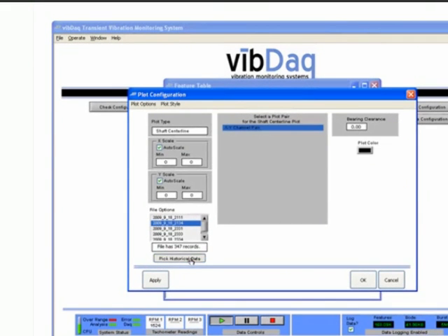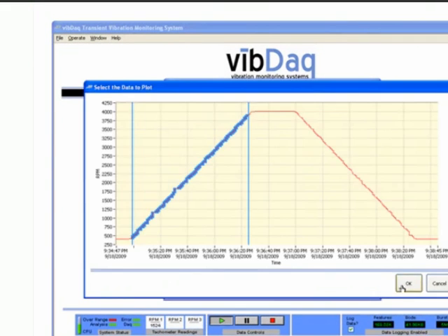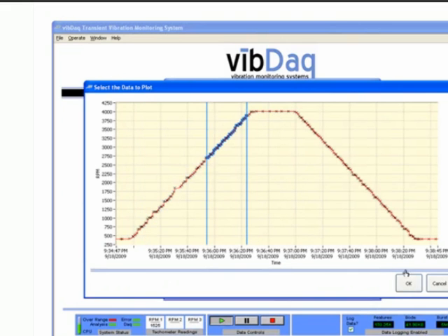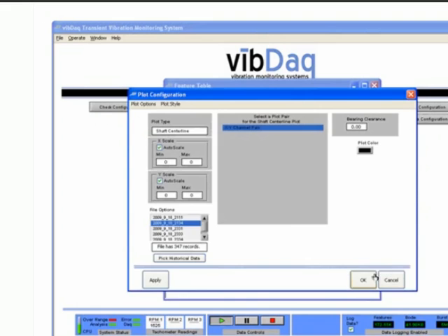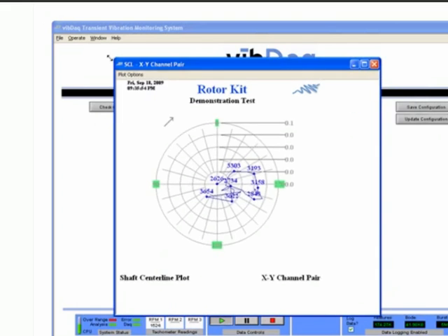Also using data from a channel pair, the shaft centerline plot shows the position of the shaft center at various speeds. The plot also shows a bearing clearance boundary. Knowing the path traveled by the shaft with relation to the boundary ensures proper operation.